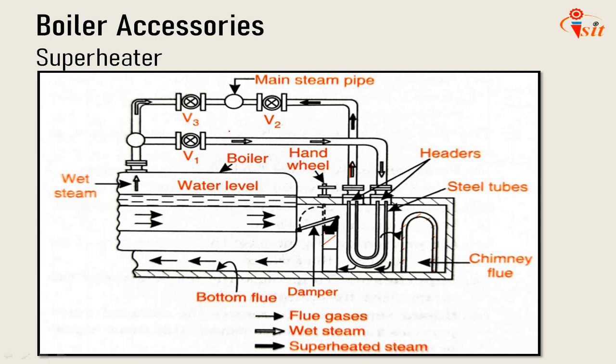There are typically two types of superheaters available. First one is convective superheater and second one is radiant superheater. Convective superheater makes use of heat in flue gases, whereas radiant superheater is placed in the furnace and wall tubes receives heat from the burning fuel through radiant process. The radiant type of superheater is generally used where a high amount of superheat temperature is required.